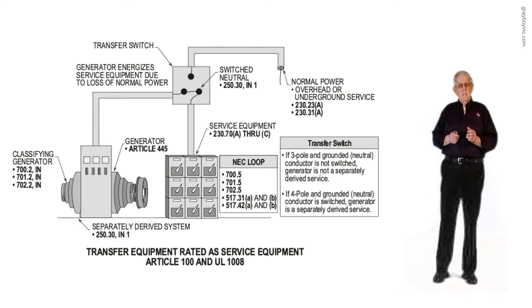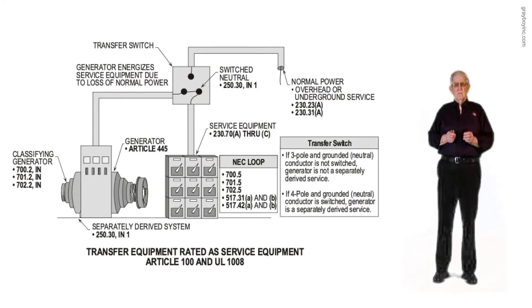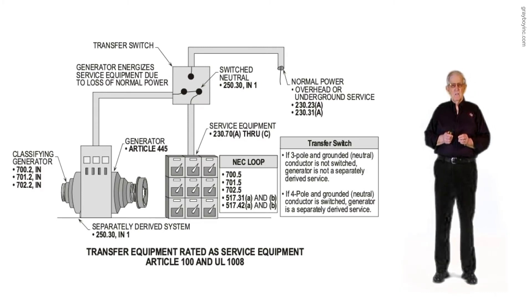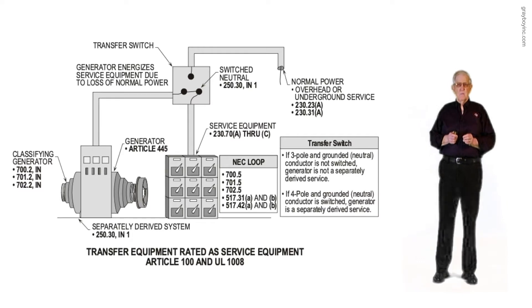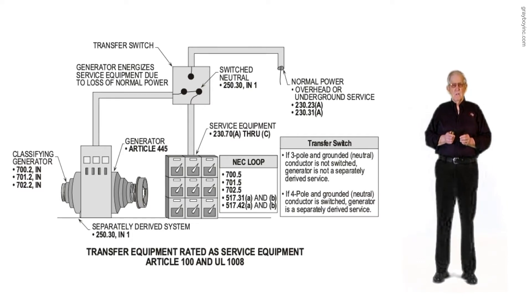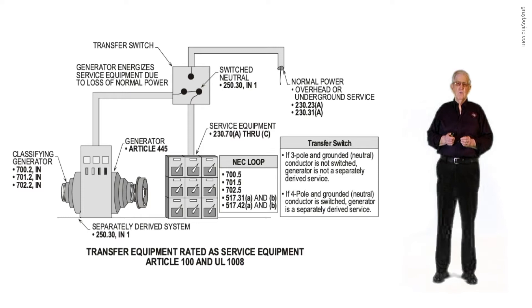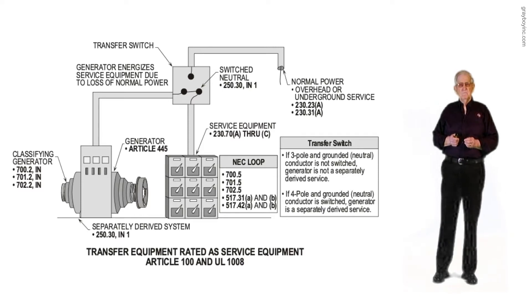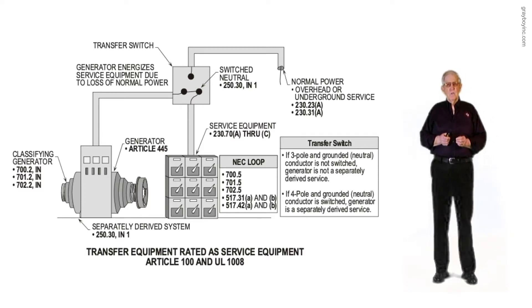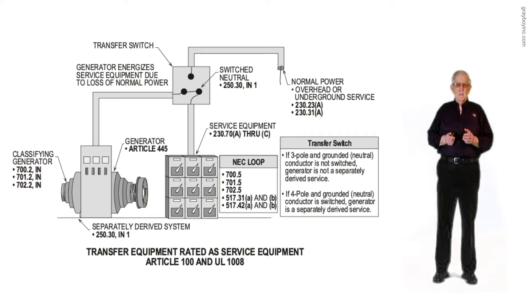Notice there's a big advantage in the classification of your generator. For example, if the generator is classified an emergency generator, that means it's brought on within 10 seconds at full power, and it also has a 15-minute delay characteristic.